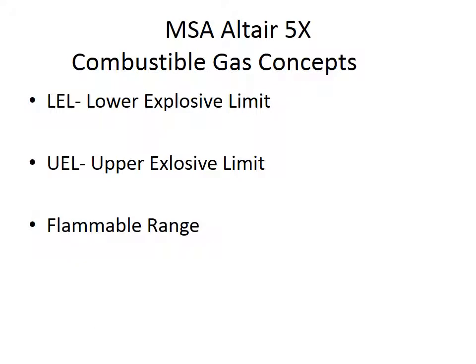Combustible gas concepts: we're talking a lot about the lower explosive limit and upper explosive limit. What does all this mean? How do we apply it to use of this meter? We're just going to go over these concepts real quick. The lower explosive limit, the LEL, is the lowest concentration of a combustible gas in air that will support combustion or an explosion, in percent volume in the air.